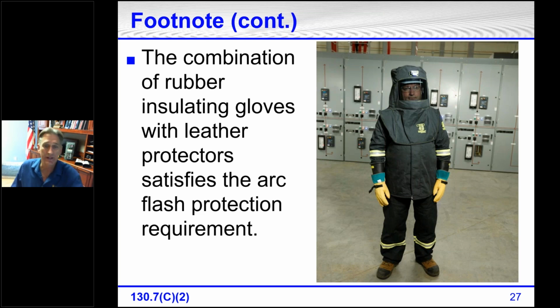Terry's wearing gloves that are class 2 gloves rated for 17,000 volts. Now, there's no requirement for a higher category to wear a higher rated voltage glove. If he was working, or I was working, in an area that would require a category 4, maybe it's 30 calories, and so I put on an arc flash suit good for 40. If it was 480 volts, I could wear the gloves rated for either 500 or 1,000. I wouldn't have to jump the glove up to be a certain heavier rubber or heavier leather glove.